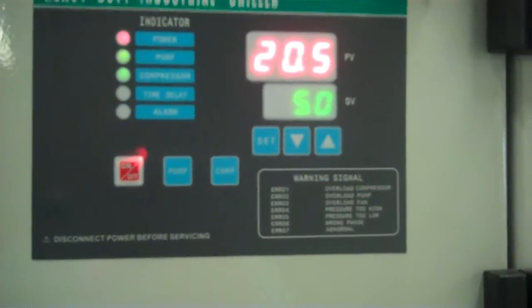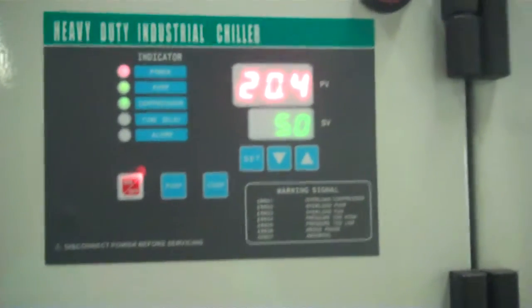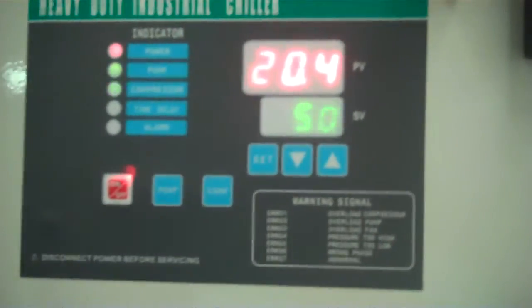One nice thing about the controller, we have different error codes here. It also has, in addition to overload compressor, overload pump, fan, pressure too high and pressure too low, it also has phase detection. So the fan, compressor, and pump have all rotation synchronized here at the factory, but if you connect the wrong phase, it won't let you start, and it simply gives you an error warning, and you just swap any two of the leads.